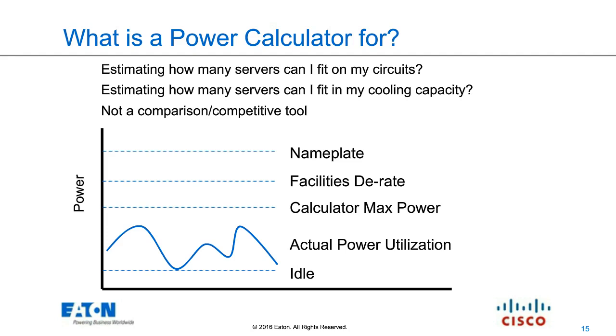Same thing applies to your cooling capacity - how much heat output will come out of these servers? So if I've got 10 kilowatts, or however many BTUs, say 12,000 BTUs, of cooling capacity, how many servers can I fit within that cooling capacity? These are very much estimation tools - they're not competitive or comparison tools.